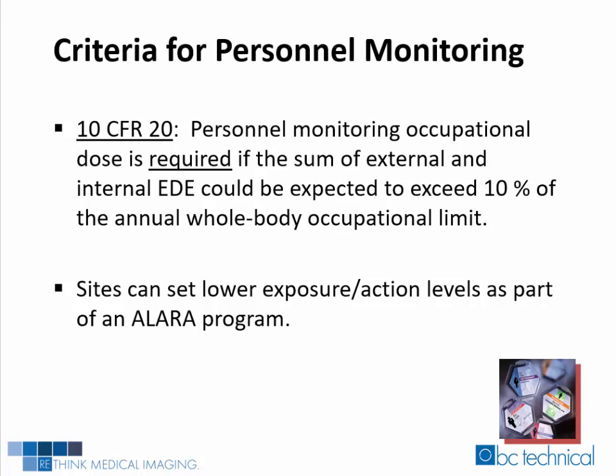10 CFR 20 states that personnel monitoring for occupational dose is required if the sum of external and internal effective dose equivalent, or EDE, could be expected to exceed 10% of the annual whole-body occupational limit. Sites can, and perhaps should, set lower exposure action levels as part of an ALARA program. Your Radiation Safety Officer, or RSO, will set the limits for your individual site. These limits can be monitored monthly or quarterly, depending on your site.